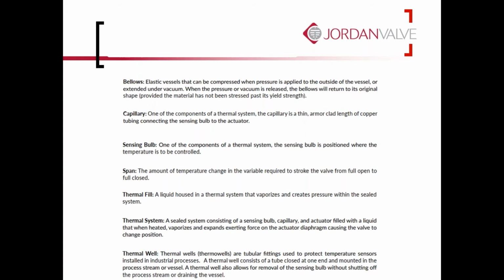And again, that's a big part of it because the stroke length of the valve and the span are going to dictate the accuracy of the valve. And as I mentioned a slide ago, that sizing is a big part of this because ensuring that you have the right CV will also help ensure that you have accurate temperature control. Thermal fill is the actual liquid in the thermal system that vaporizes and condenses to actually stroke the valve. And fills will vary based on temperature requirements. The thermal system is all of the components listed above. So the sensing bulb, the capillary, the actuator, all of that will have this thermal fill in it, and that is considered a thermal system.